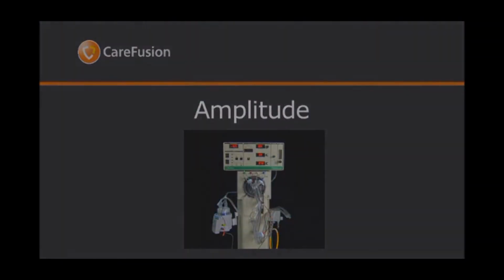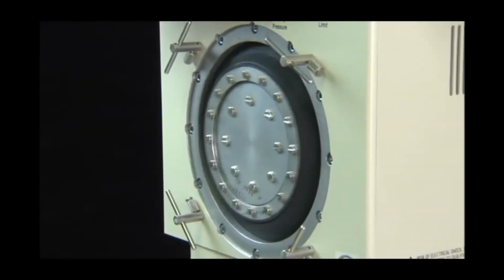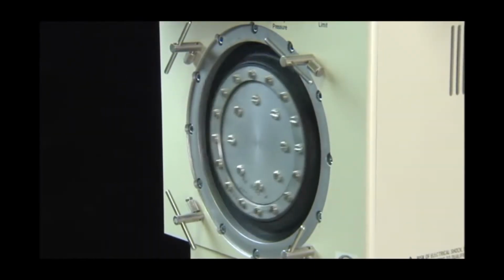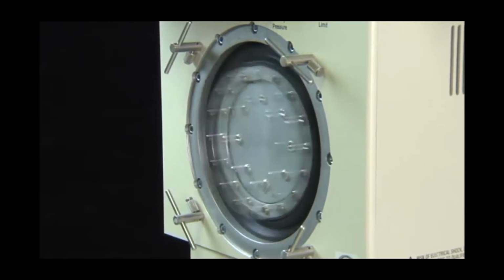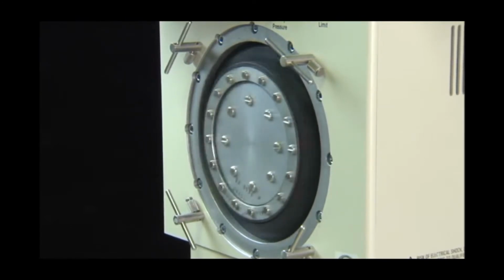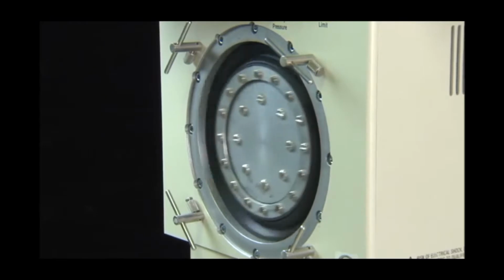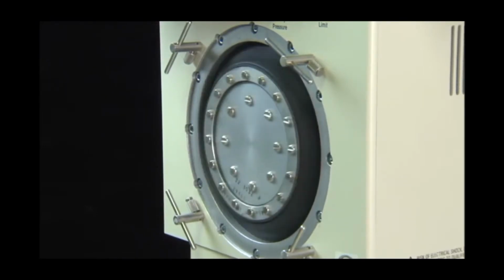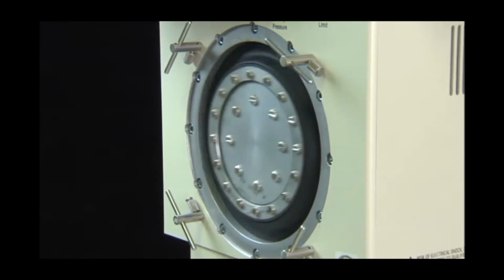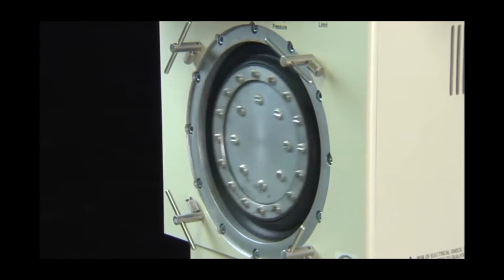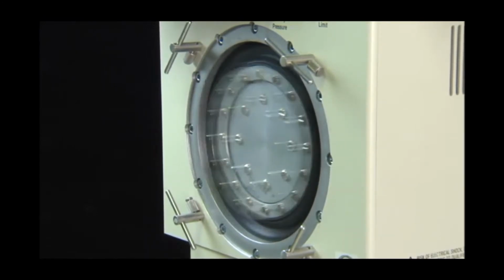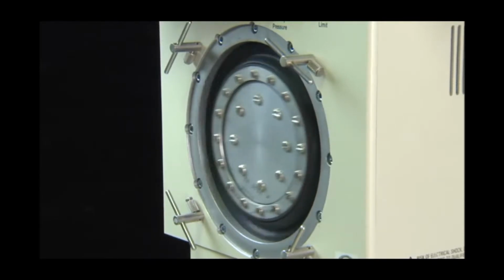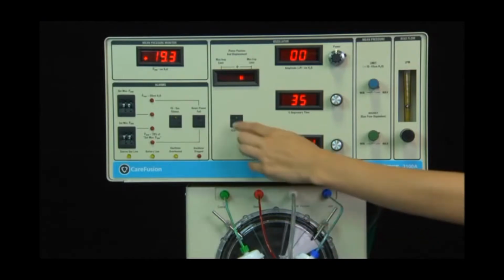Amplitude. An electronic control circuit driving a linear motor produces the oscillatory amplitude in much the same way as in a permanent magnet speaker. When the square wave driver has a positive polarity, it drives the electrical coil and the attached piston forward in the direction of the patient. This results in an inspiratory phase. When the polarity is negative, the electrical coil and the attached piston are driven in the opposite direction, resulting in an active expiratory phase. To activate the oscillator, press the Start-Stop button.